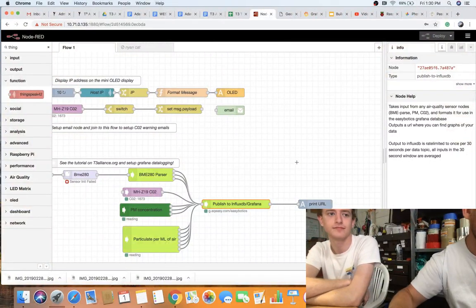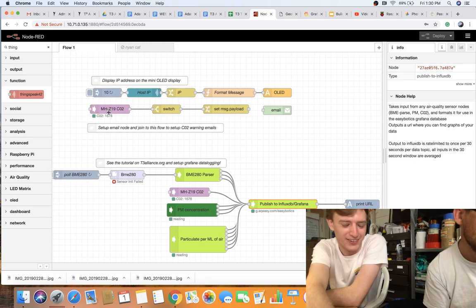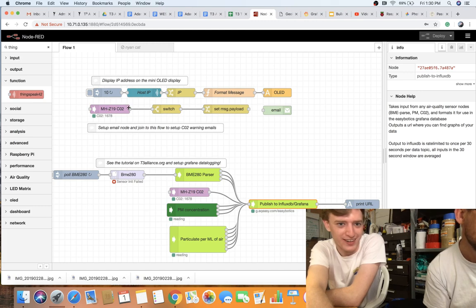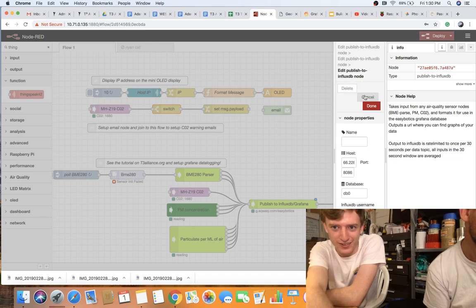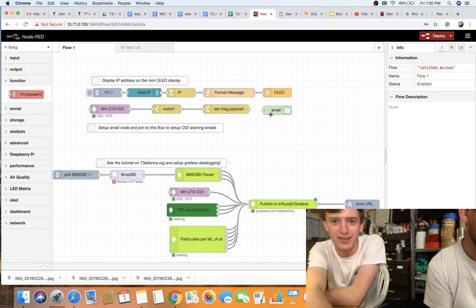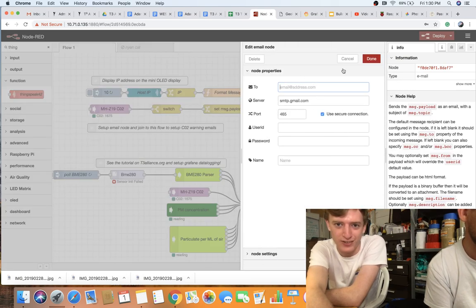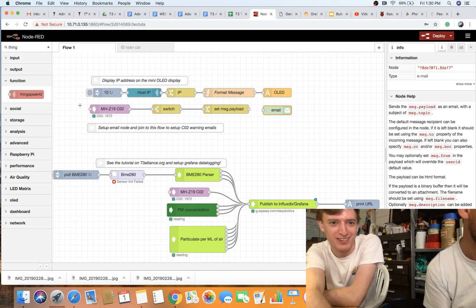If you want to add an if-then scenario, there's an example set up here that sends an email. The CO2 sensor node comes into a switch node that says: if the payload is greater than 1200, send it through. Then it sends an email saying 'CO2 levels in offices have risen above the CDC recommended level of 1200.' This comes into an email node that actually sends a Gmail, which you can set up with your own Gmail account. That's just one example of an air quality related action you can automate.